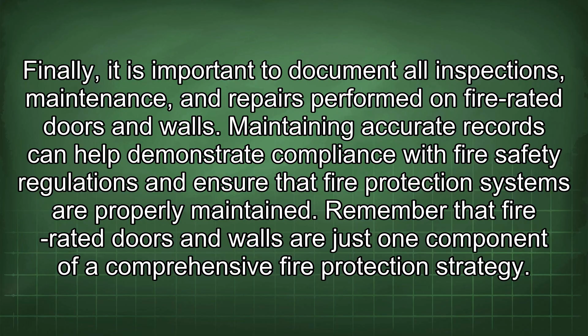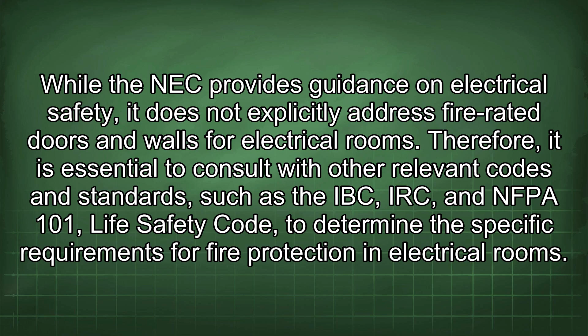While the NEC provides guidance on electrical safety, it does not explicitly address fire-rated doors and walls for electrical rooms. Therefore, it is essential to consult with other relevant codes and standards such as the IBC, IRC, and NFPA 101 Life Safety Code to determine the specific requirements for fire protection in electrical rooms.